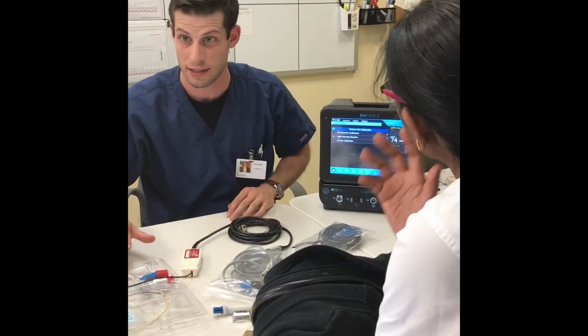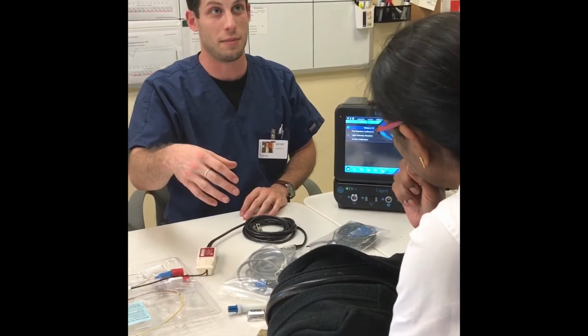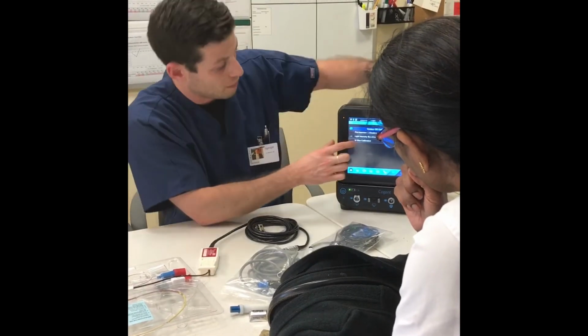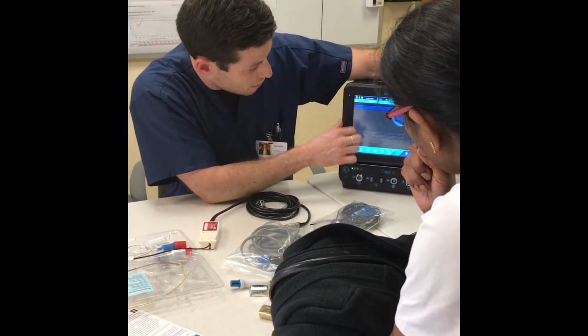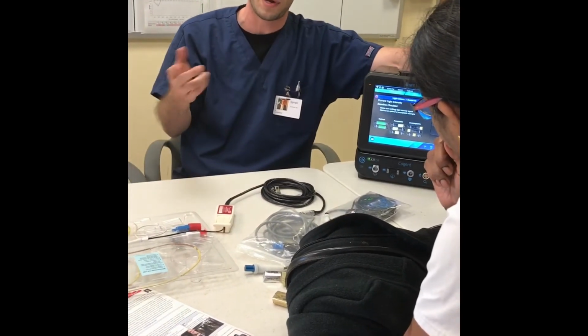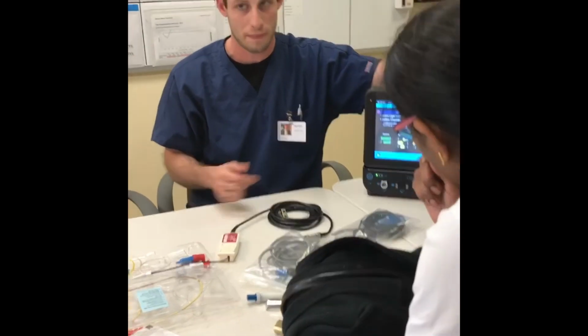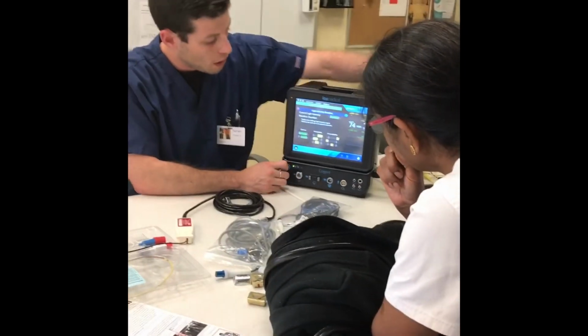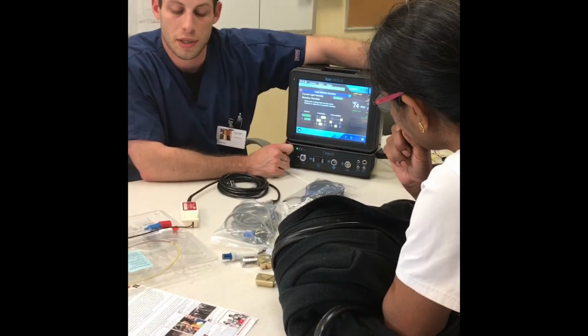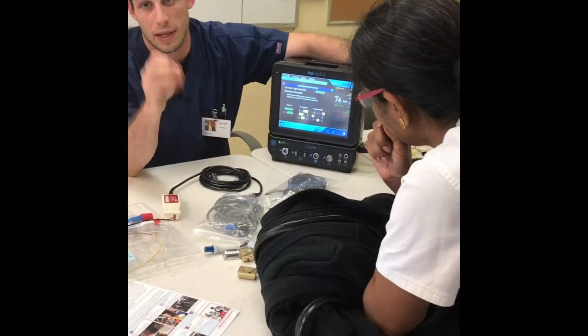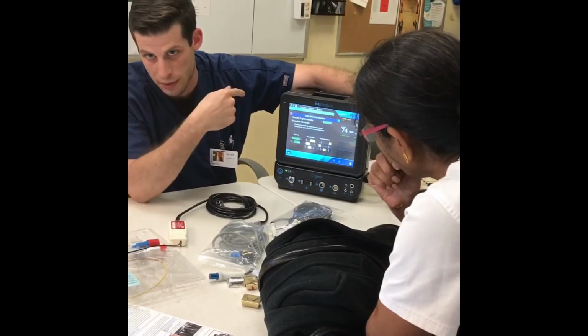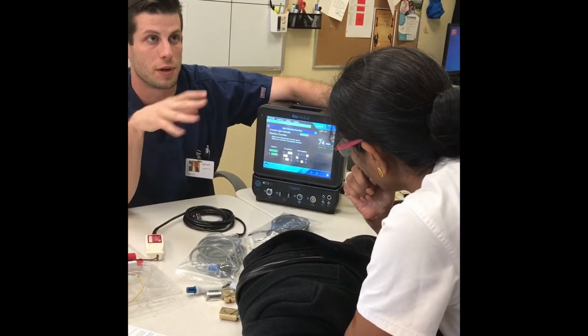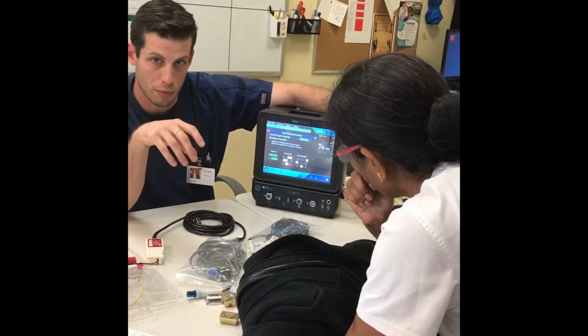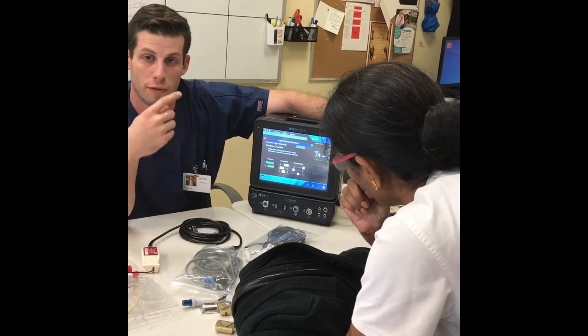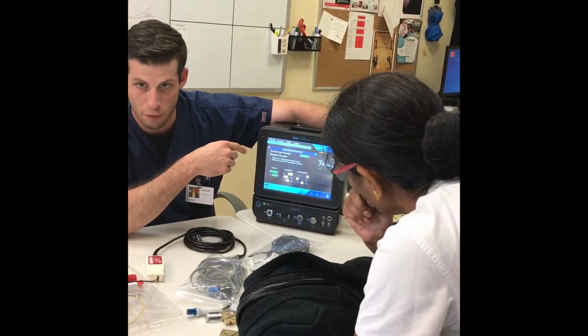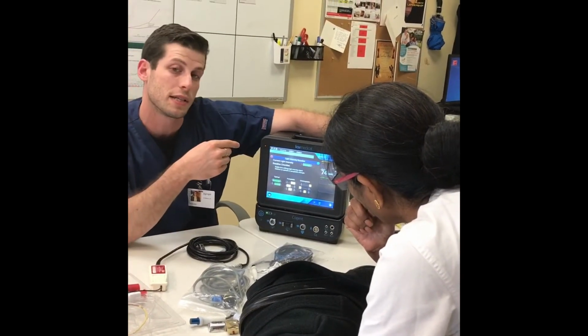Now, prime your lines, get it ready, get the catheter in the patient. Good? Cool, keep going. Now you're going to do the last part, light intensity baseline. Remember I brought up earlier how the monitor is going to tell you whether the numbers are good or not? Here's the image. The light intensity baseline is checking that the blood is flowing past the tip of the catheter. We're sending out light and taking back the light and reading it on this. With the pulmonary artery, it's very branched, and there's a lot of small branches. The smaller branches don't have flowing blood per se. Sometimes it's more of a pooling type blood. That's what we're watching out for. We always want you to sit in flowing blood, and your light intensity baseline is what checks that for you.